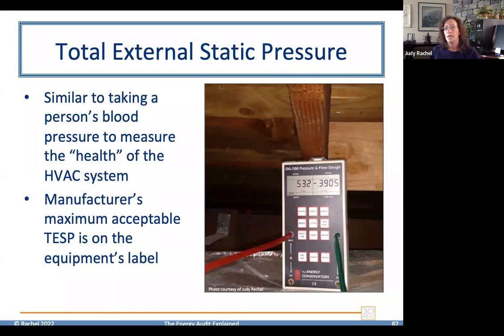External static pressure is another great test to do on our heating and cooling system. It's kind of like taking your own blood pressure, telling how well that system is operating against the components that are hooked up to it. The air handler that comes from the manufacturer is rated for a total external static pressure, and everything attached to that air handler, from the evaporator coil, a filter box, the whole duct system, the supply and return plenums, the grills, everything past that is adding resistance and pressure against that air handler.